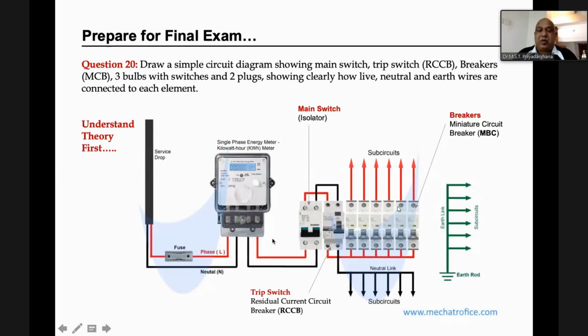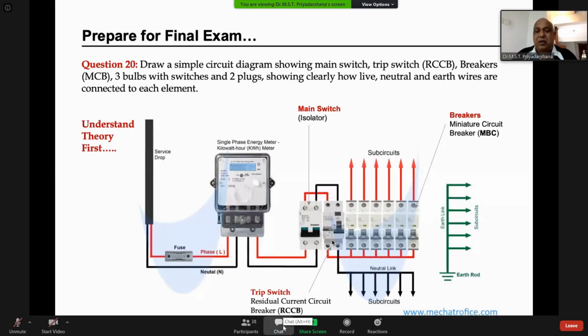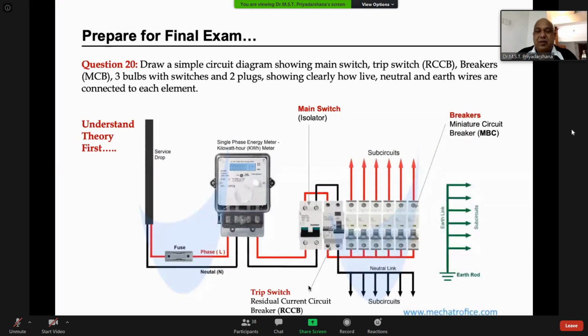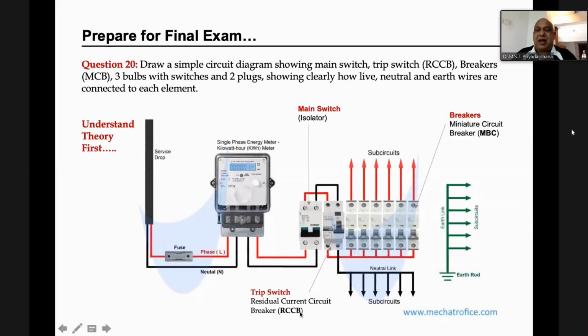So you can see clearly, these 2 lines go through the main switch, and then go through what? The trip switch. Both lines go through the trip switch. Then you take out these 2 lines from the trip switch. The trip switch is the RCCB, as we previously discussed.